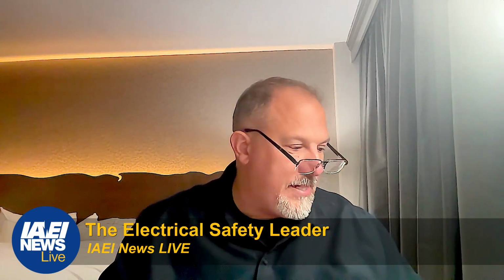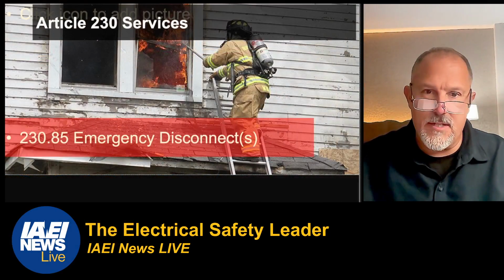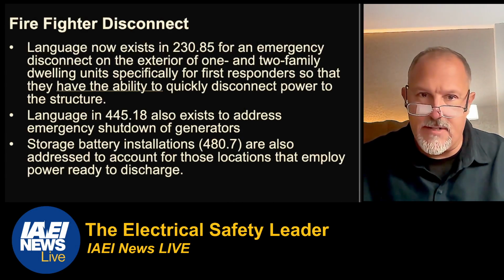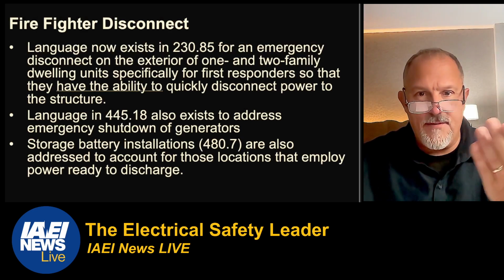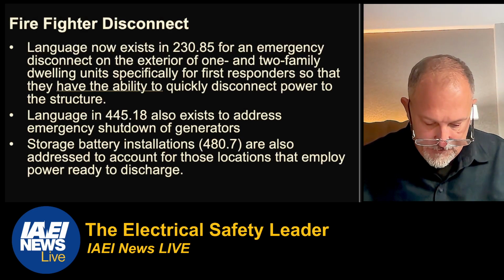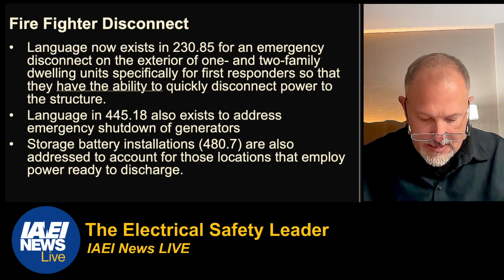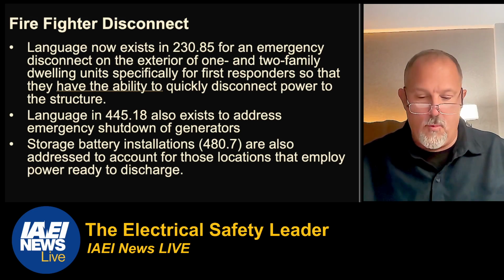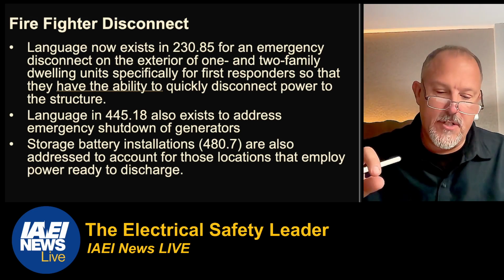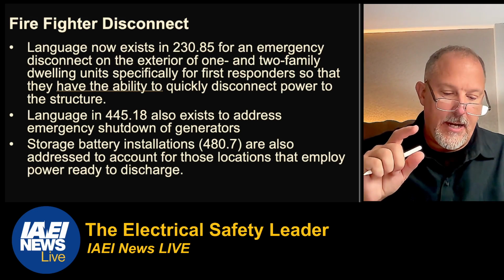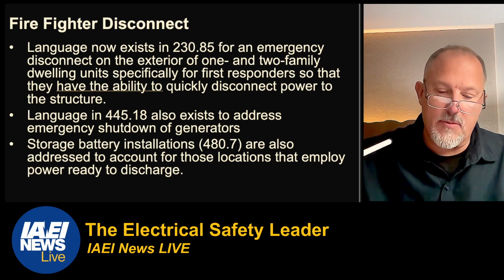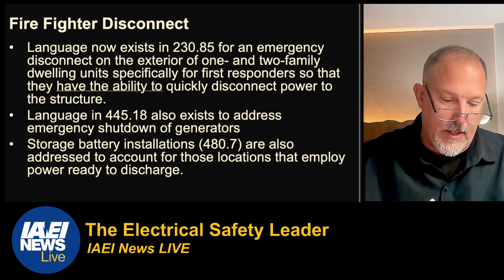So that's a big change. Emergency disconnects. Remember, we called it the firefighter disconnect. So we have 230.85. Now, I'll tell you, here's what's happening. You have emergency disconnects for 1 and 2 family dwelling units. An emergency disconnecting means shall be installed. The disconnecting means shall be installed in a readily accessible outdoor location within sight of the dwelling unit.